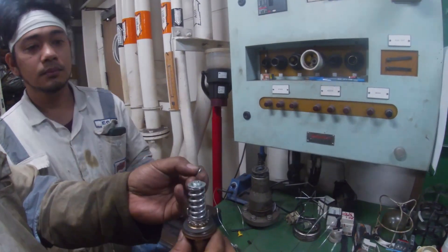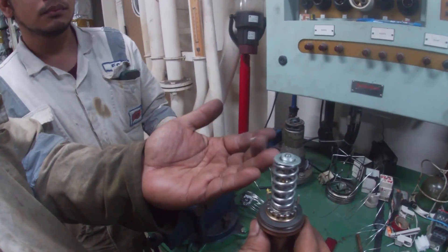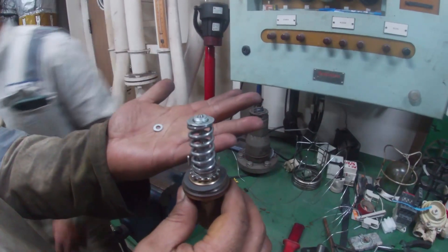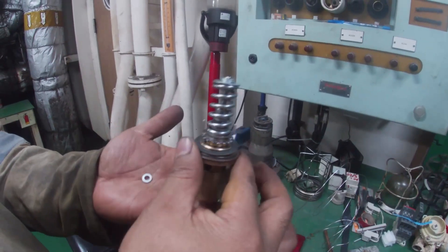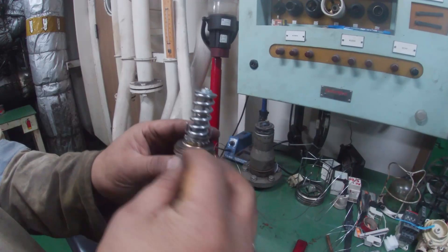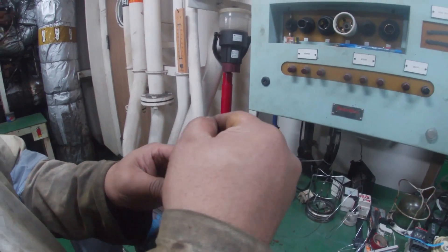So since the diaphragm is damaged and we don't have a spare, we will try to manipulate the opening of the expansion valve by inserting a washer, so when put in the housing it will automatically remain open without any control.